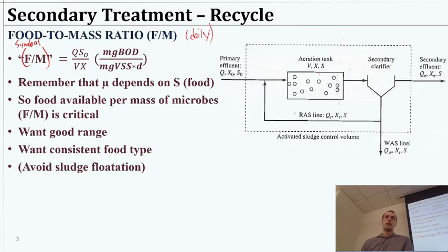It's a compounding problem, and it's a problem that wastewater treatment plants do deal with sometimes, and it creates a range of problems, including untreated waste leaving, lots of bacteria leaving, and bad smells because now you're no longer necessarily getting all that aerobic process done, which smells kind of earthy. It's maybe a little unpleasant, but not a lot unpleasant if you have a properly running aeration tank. Whereas if you have some anaerobic processes going, that's going to be very unpleasant.